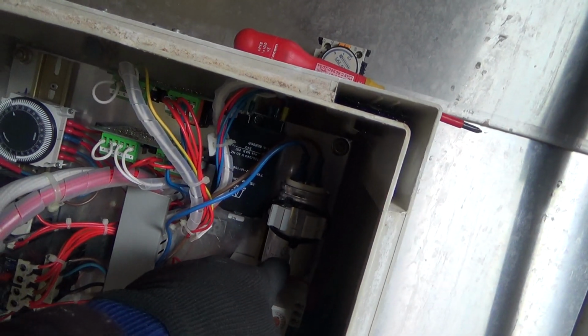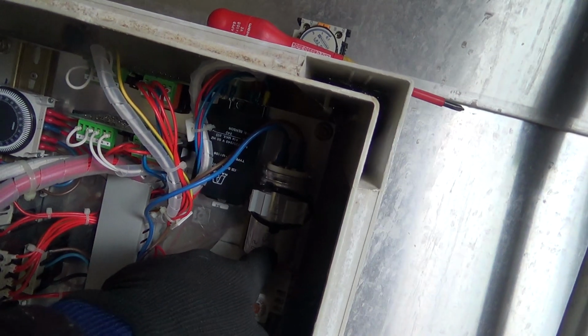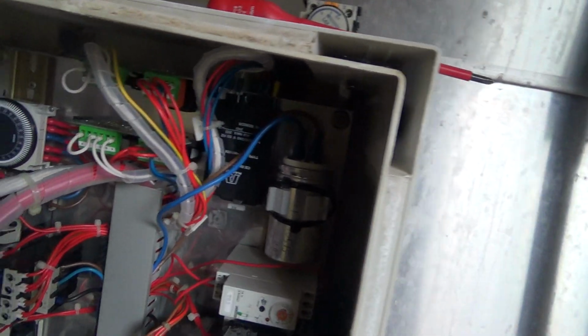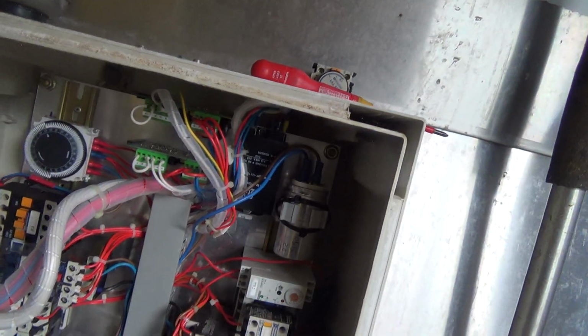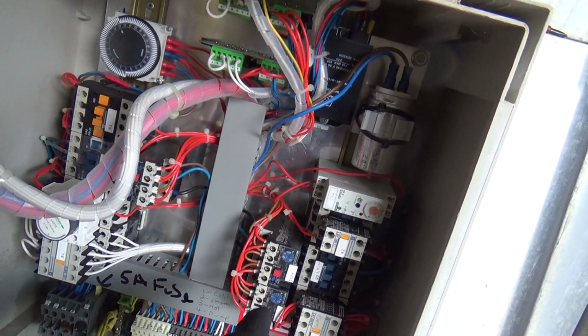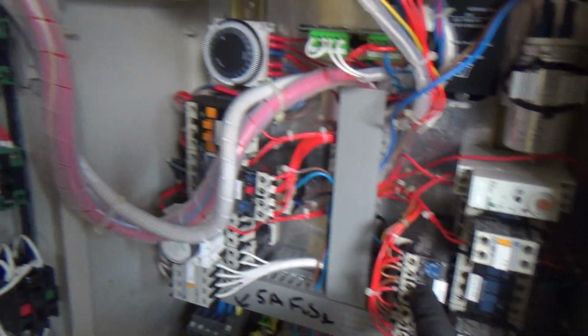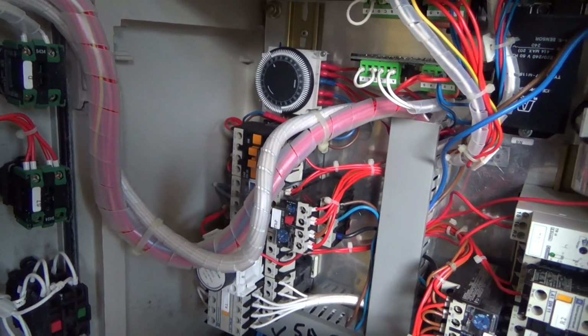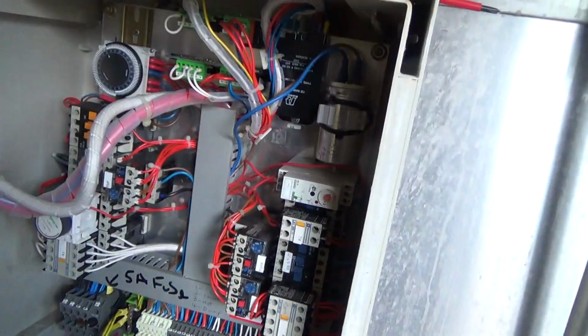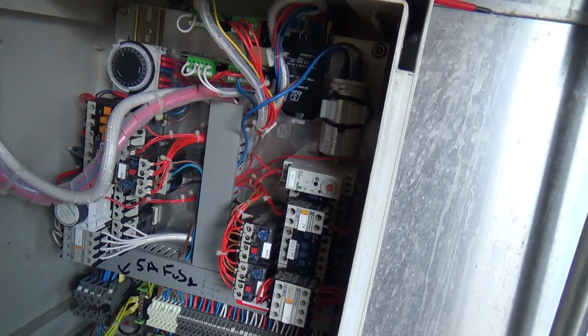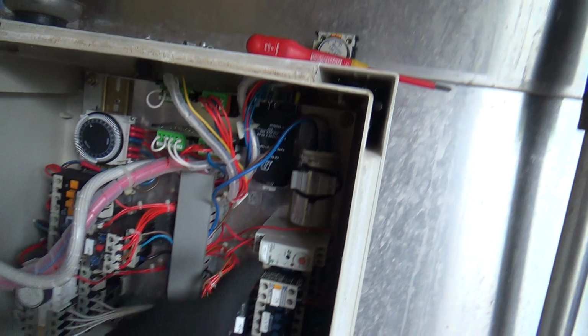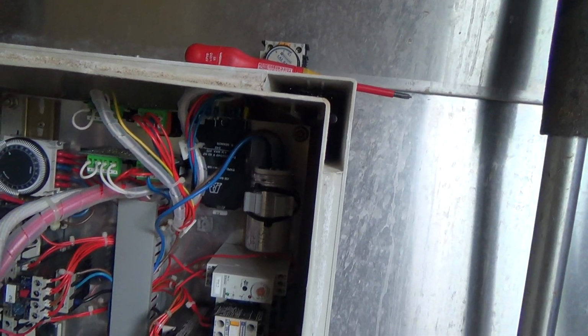And then the only other thing that's worth checking is the capacitors. We've got one for the chilled water pump, I think, or that might be the wash pump. I think that's the chilled water pump. And one for the agitator, because if they go, it'll trip the overloads, which are usually set to automatic reset on here. If the overloads trip, it shuts the whole cooling down and the display goes blank. Then when the power comes back on, it does a little self-diagnostic, but that can take a few minutes for it to reset. So if it keeps doing that during milking, you're not going to make any ice, and that is quite often when these get weak, so we'll check those.